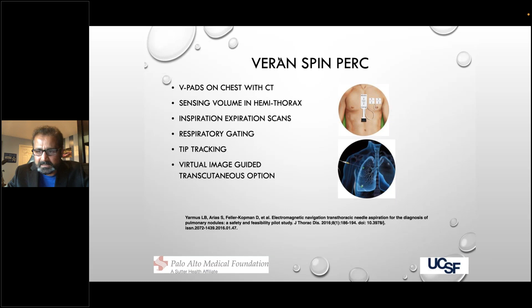But the interesting thing is that we learned a lot about CT to body divergence by this hemithoracic volume assessment. We learned that changes happening on one side of the thorax affect the other side, and therefore having a hemithoracic volume assessment is not exactly the best way to go in a sensing volume-based, electromagnetism-based platform. And also, we know that tip tracking within the sensing volume is only a single point tracking, which can also be problematic, and which subsequently improved in other systems that came on later.